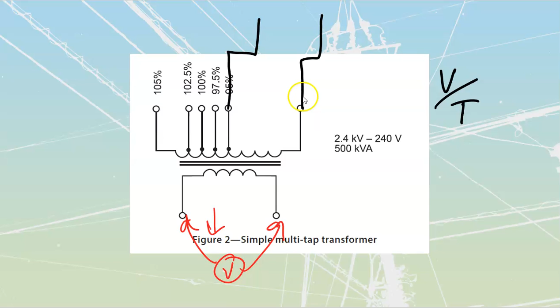We're going to look at both of them, but really what these on-load and no-load tap changers do is take an individual lead off of every single one of those taps. In other words, when you initially install this, you take a lead from here to the on-load, a lead from here, a lead from here—you're going to take six leads for each of these windings. This is a 3-phase transformer. It's just the best picture I had of decent-sized taps we could zoom in on here.